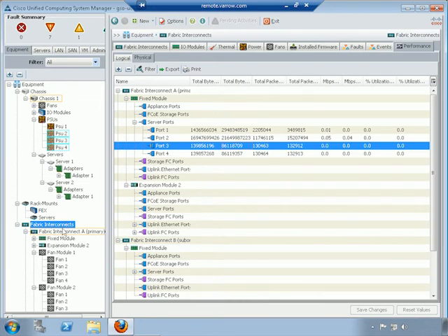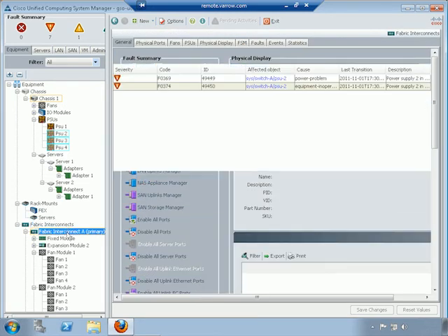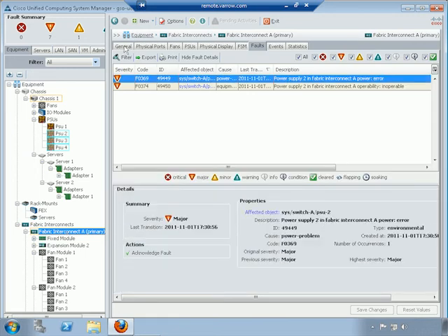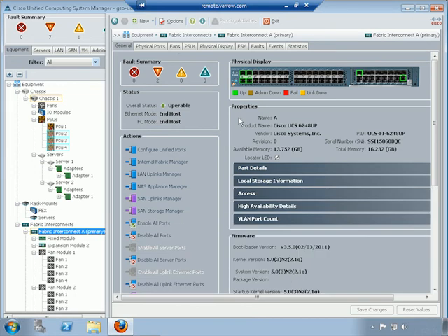So let's see. We can drill down to a specific interconnect. Go back to the General tab again, and you get that kind of front view of the interconnect. If something is red or green, you can look at it and tell what it is. So if I highlight this, it says Ethernet port 13, type is server. Server ports go down to chassis. This is 2.1 and it's network. That's going up to the core network. And 2.16, is that also network? Yes, that is also network.